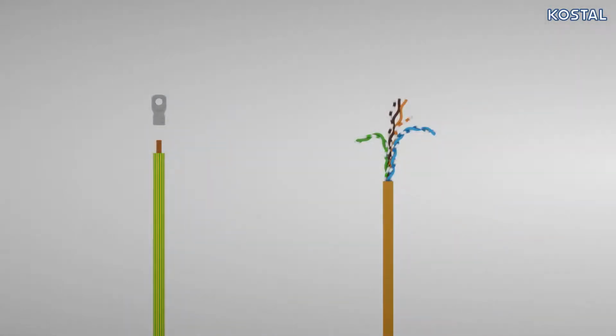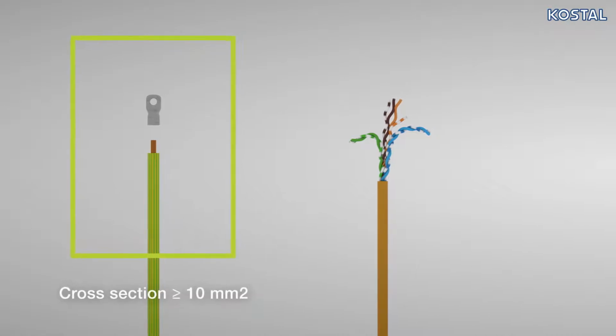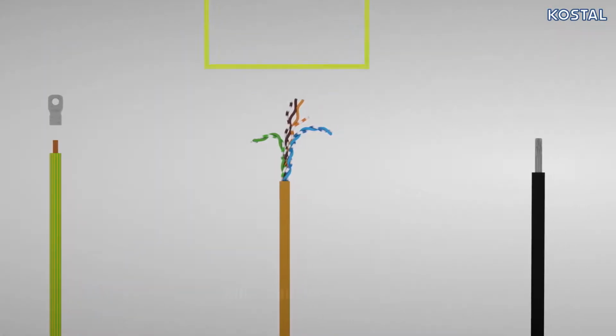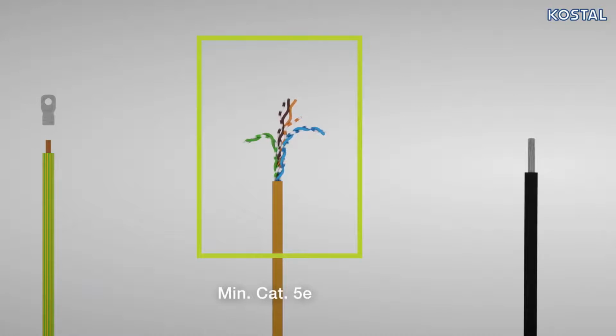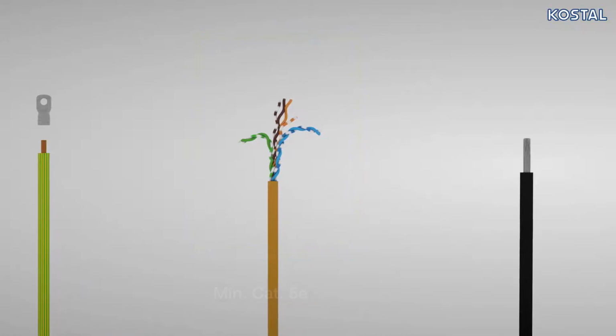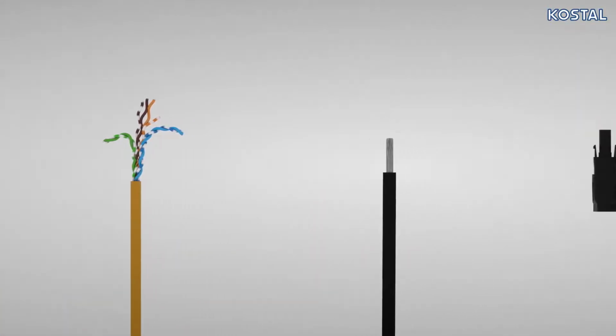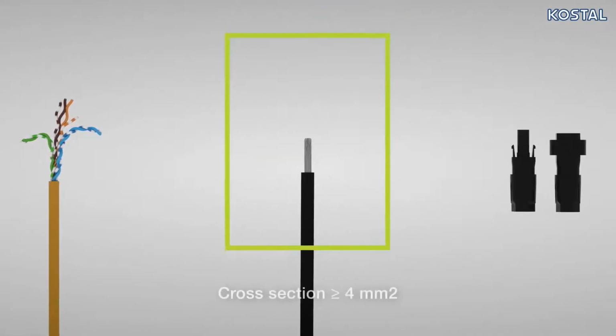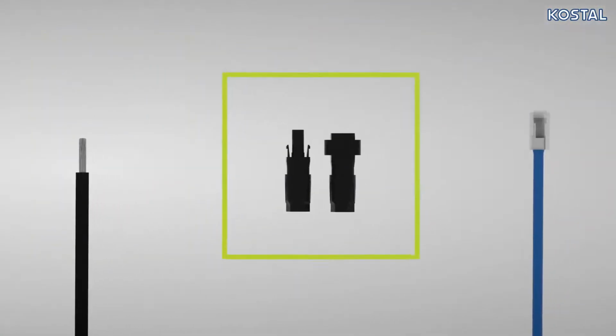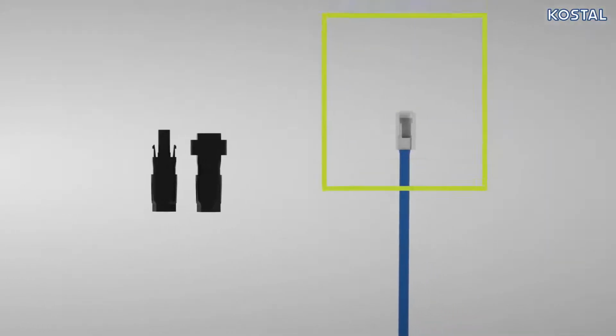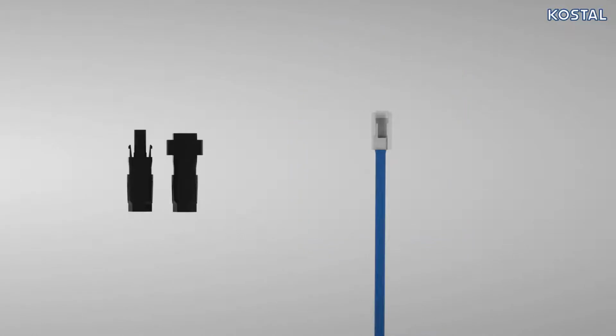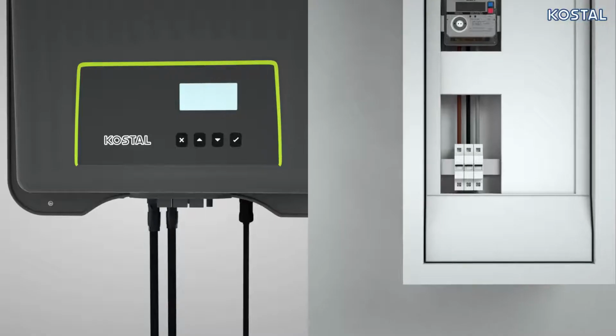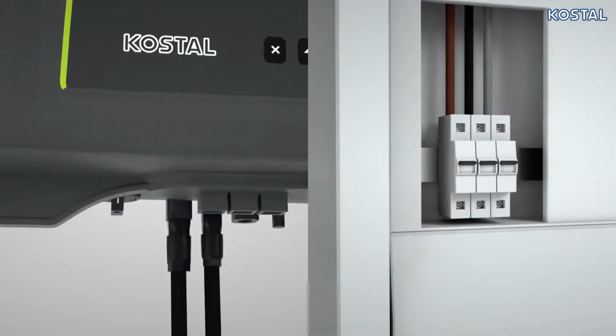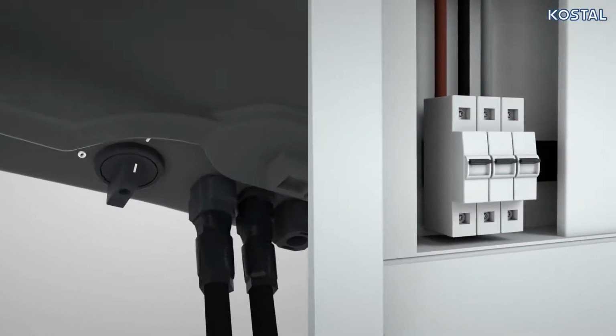During installation, you will need protective conductor cable with cable lug to fit, a network cable for the communication connection between the KOSTAL Smart Energy Meter and battery, PV cable for the DC connection, and a pair of SUNCLIX plugs from the inverter accessories, as well as an optional network cable for connecting the battery to the internet. Before getting started, switch off any components in your PV system that may already be running.